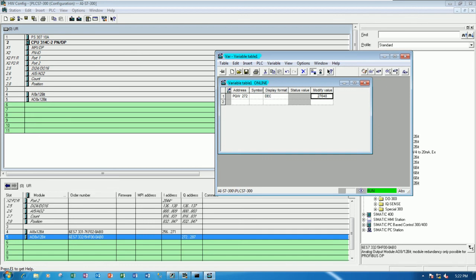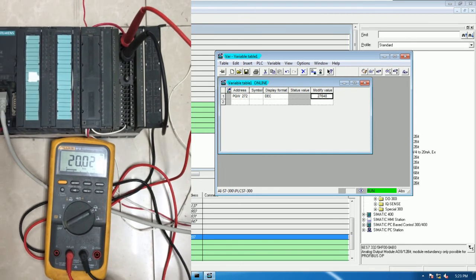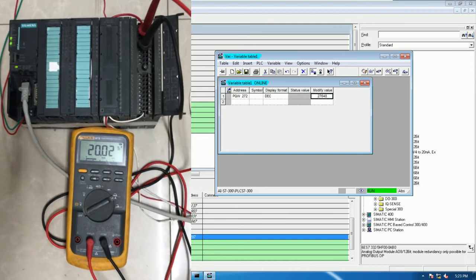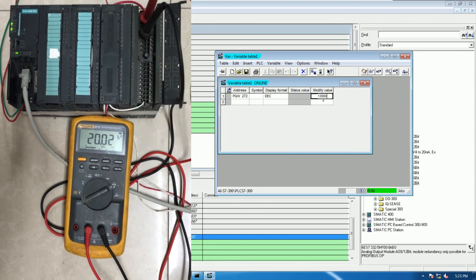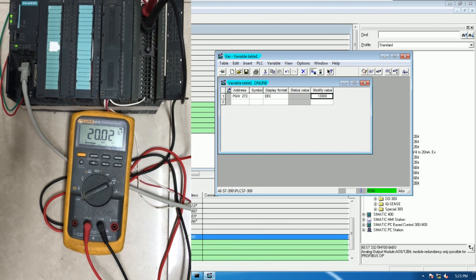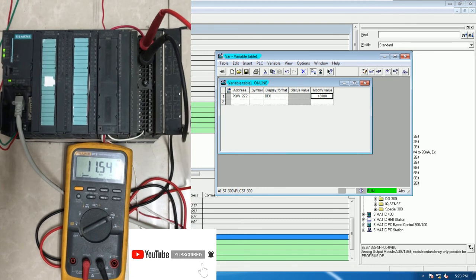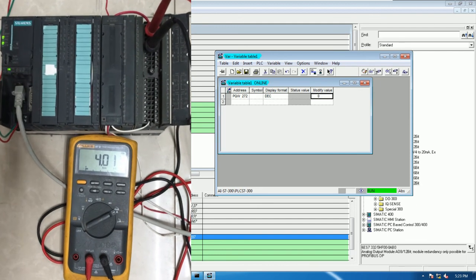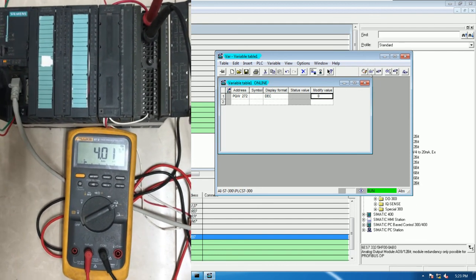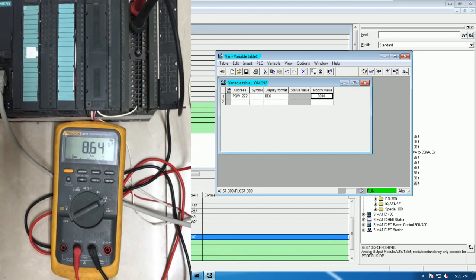We will get 20 milliamp — I will show on the multimeter. Channel number 0 shows 20 milliamp. I will decrease the value — for example 13000. Let's see — around 11 milliamp. And if I set 0, it will show around 4 milliamp. For example 8000, it will show around 8 milliamp.